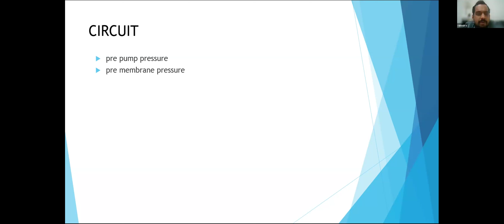Clots in the oxygenator: daily there should be a flashlight test on both sides, pre side and post side of the oxygenator, so as to identify the clots at an early stage. Chattering: whenever there is hypovolemia or hypotension for the patient, what will happen? The venous end of the cannula will start chattering for the flows given here. So once you think the circuit is chattering, try to come down on the flows a little bit and see whether the chattering is settling or not. If it is settling, that means it's mainly because of hypovolemia. Try to correct the volume status of the patient either by crystalloids or blood transfusions.